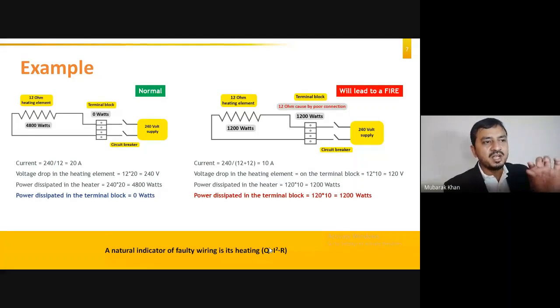Now in this case, what will happen? The 240 volt power supply will try to supply the heating element, but because there is a resistance in between, the voltage will be distributed between the terminal block and the heating element proportionally, depending on the resistance, according to Kirchhoff's voltage law. I hope you remember Kirchhoff's voltage law - if not, it's very simple: the summation of all the voltages in a loop is equal to 0. So the 240 volt supply has to be proportionally distributed between the two, such that the supply voltage minus the voltage drops should equal 0.